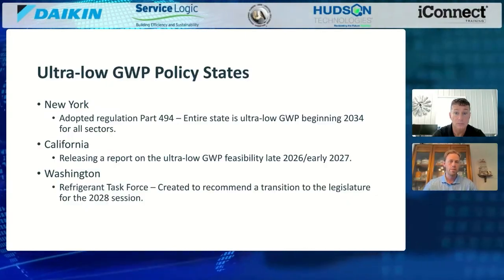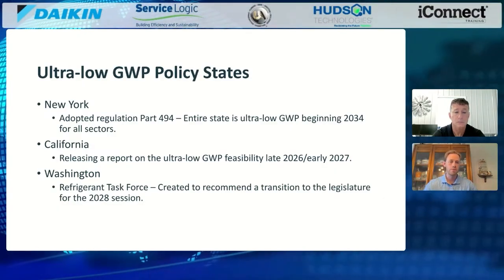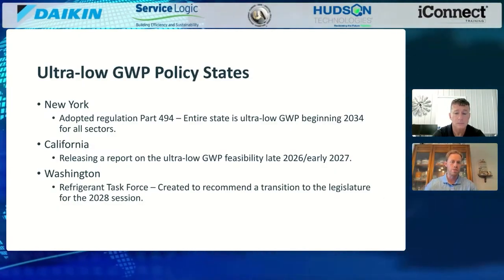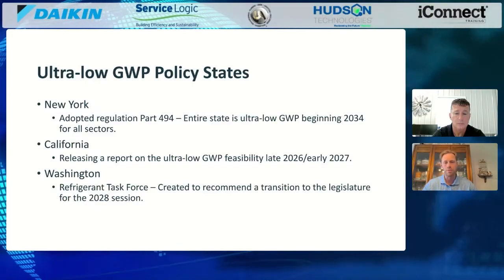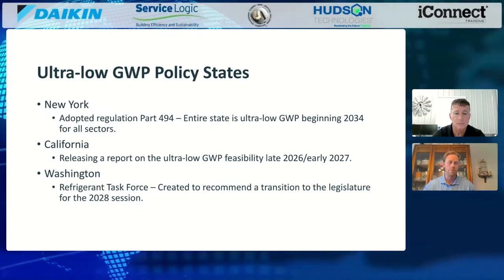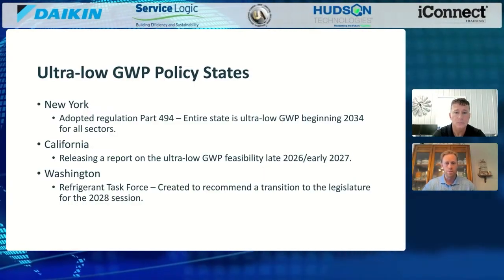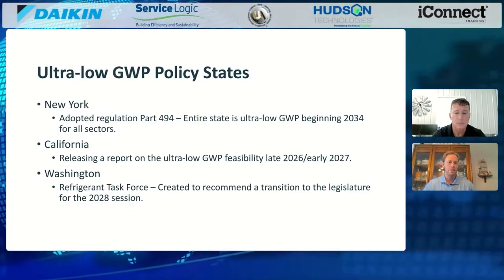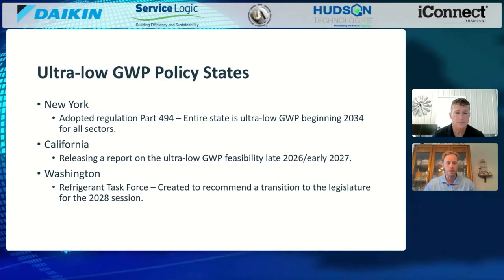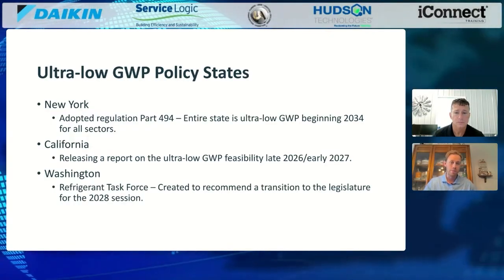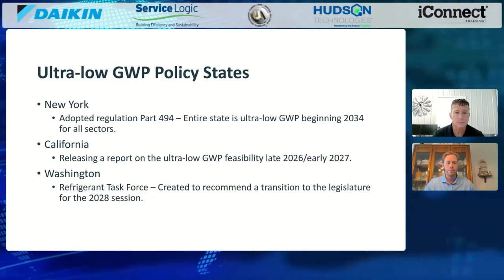specifically supermarkets, just because it exists doesn't mean it's feasible for adoption, because of, like you talk about, rebates and the costs of all these efficiency tiers, adjusting and ripping out entire systems to accommodate the high pressures required for CO2 from your 404A, 507A. Those can be business ending. Millions and tens of millions of dollars. Yeah, you have to prepare for that kind of stuff. And if you spring something like that on a New York supermarket, especially the independent ones in the food desert areas that exist right now upstate, it can be devastating.